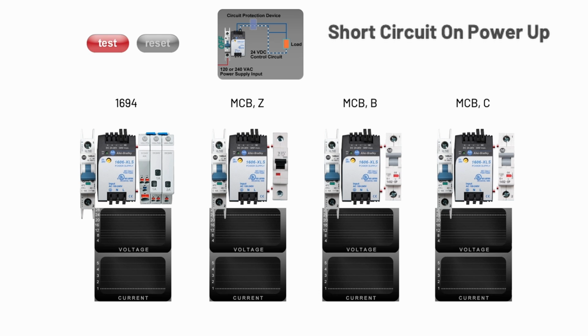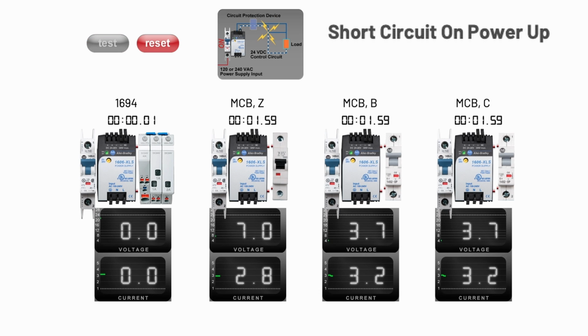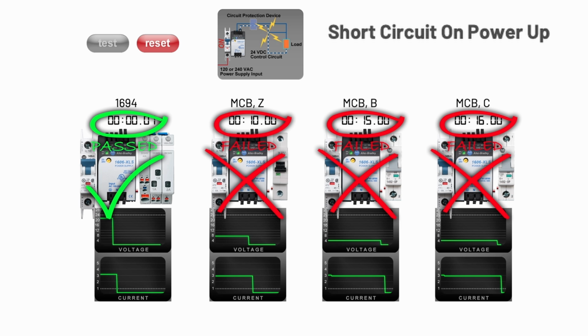The first simulation represents a short circuit and how each device will respond upon initial startup of the power supply. As you can see, the ECP detected the fault and tripped the protector in 0.01 seconds. Because the DC power supply cannot provide enough current for the miniature circuit breaker to operate, it took between 10 to 16 seconds for them to trip. This is more than enough time to potentially cause damage to the wiring or connected devices.